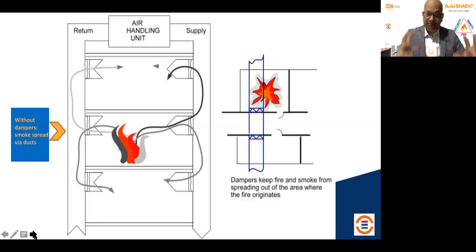Now, if you have an AHU system, typically in a high-rise building, and you don't have dampers, what will happen? This is how it will happen. You have a supply side and you have a return side, right? Air handling unit. Supply means that is what is supplying the air and taking out the air from this specific area. Now, if there's a fire on the second floor and you don't have dampers, immediately it will take from the supply side and take the smoke to the adjoining floor. So this is what happens when you don't have smoke dampers in your AHU systems zone-wise. Vice versa, if you have dampers in place and there is a fire here, what we are doing is shutting that damper so that the smoke will not travel from this floor to the other floor.